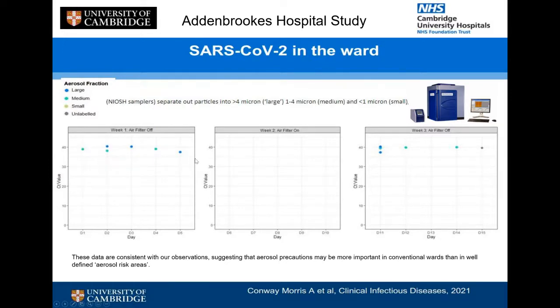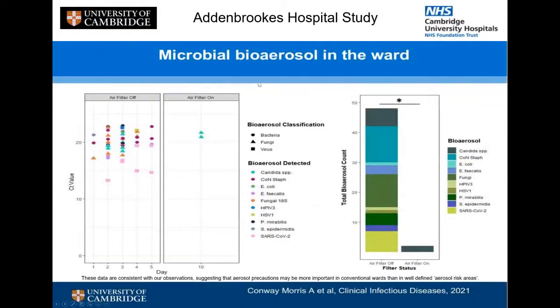COVID aerosols were being measured in the larger particle size; filtration on, and they disappeared; filtration off again, they registered again. A clear benefit for standalone air cleaners. But they also monitored general levels of bioaerosols, not just COVID-19, but all these other airborne particles gathered by the samplers, which again would lead to the indication that maybe air filtration should be more generally used in the indoor space of hospitals if you are having this situation where you have a large virus and bacterial particle load in the atmosphere, which can be drastically reduced.